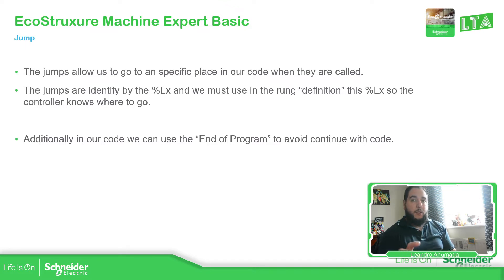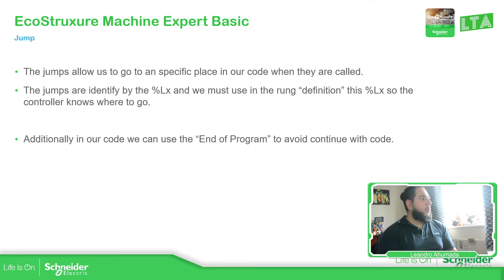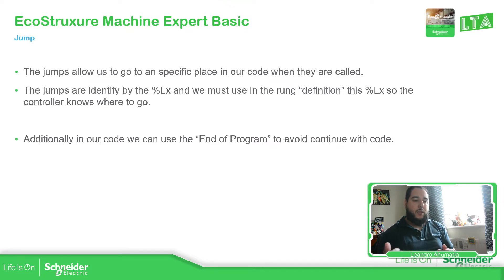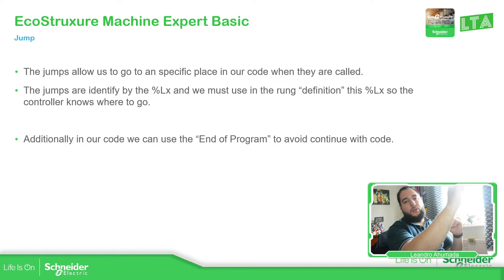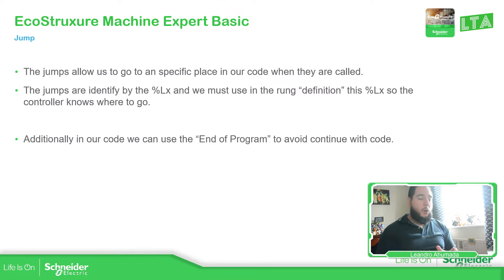There is a specific element for the jump and we need to introduce the percentage L, which I believe is for label. This percentage L must have a number. Based on this label, it allows us to indicate on the left side of the rung where we want to jump. So I have my rung with the code and then I execute the jump with a specific label, and that label allows me to go to any position that I want in the code.